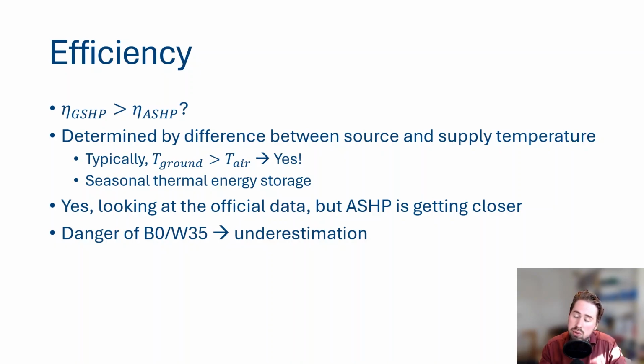But if you design a ground source heat pump with your bore field correctly, you typically don't get these temperatures of 0 degrees. So you're typically higher, meaning that your efficiency is also higher. So that's a reason why you should pay attention, because the efficiency of your ground source heat pump is typically somewhat higher than your official efficiency.